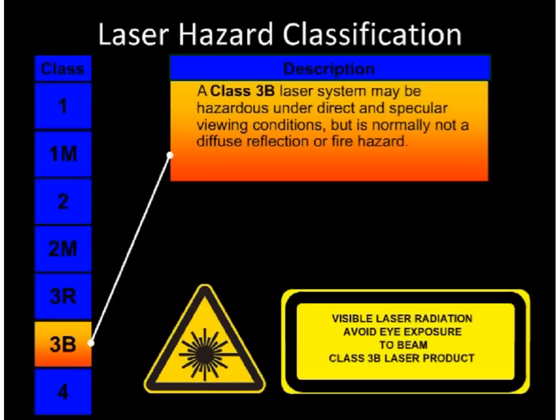Class 3B. Eye damage is likely to occur if the beam is viewed directly or reflected from a shiny, mirror-like surface, including an accidental or momentary exposure. If the laser emissions are near the upper limits for Class 3B, the laser light might be capable of producing minor skin injuries or even pose a risk of igniting flammable materials.